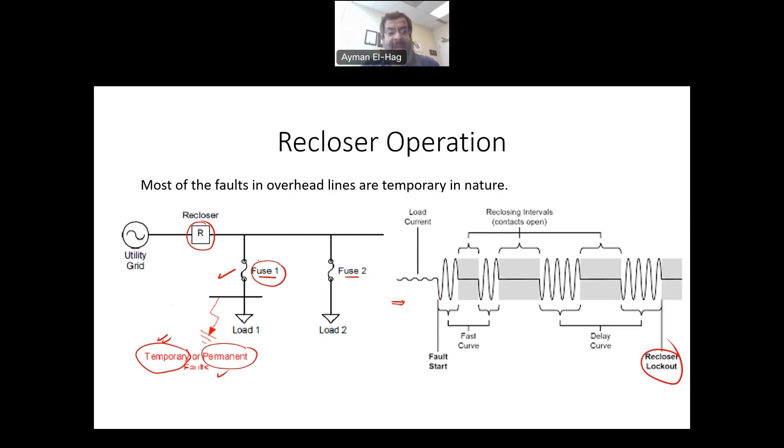But if the fuse activates, only this portion will lose power and the Recloser will be closed circuit and power will be fed to the other loads. So that is a brief description of how the Recloser operates and how it is coordinated with the fuse.